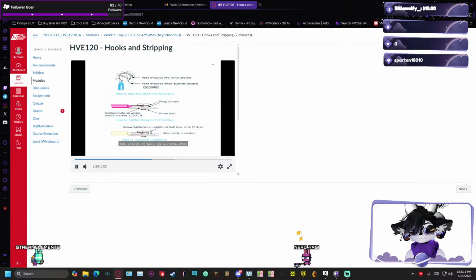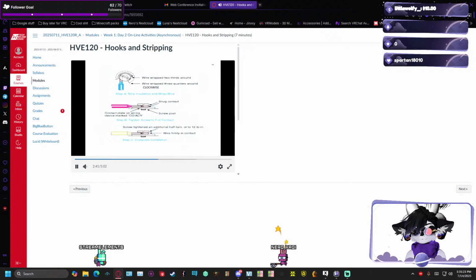Also, when you tighten or torque your screw down, typically you tighten the screw down until it makes good solid contact, and will turn a 1/2 turn after that. That should be more than sufficient. The actual torque spec is 12 inch-pounds, so you don't need to go beyond that or strip your screw out to get a good connection.